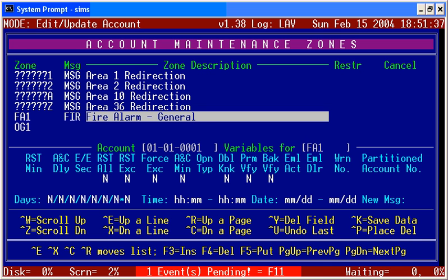So even though they're sending you a user 1, you may not know who it is inside of the SIMS2 database, but the fact that they transmit the name in with it will allow it to be written into history and actioned on the screen just as if it were in the database. And in the SIA level 3 case, if it's a fire and they actually transmit some other information about the fire, wherever this fire zone is located and so forth, it will appear in the dispatch and action screens up on the traffic display. This is much the same fashion that we deal with the DMP formats and the transmission of English language there.